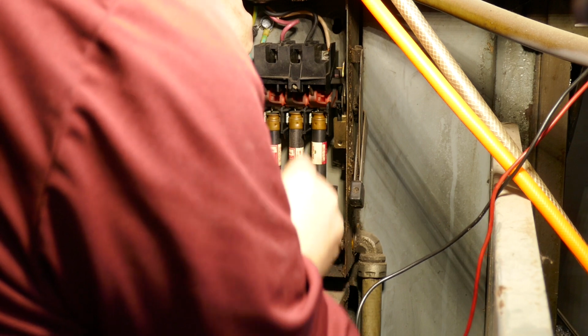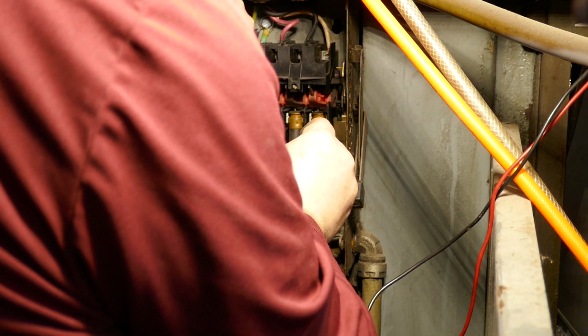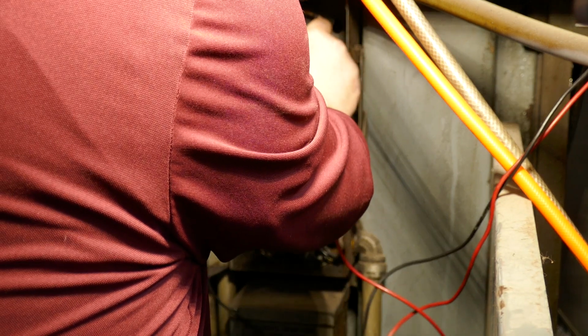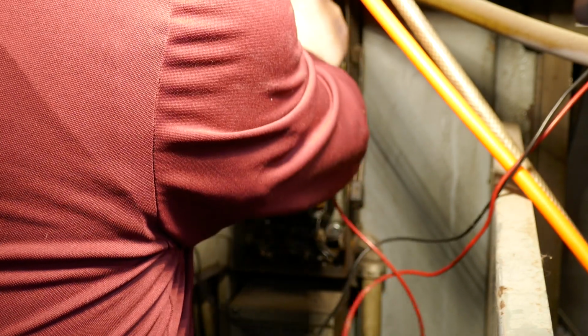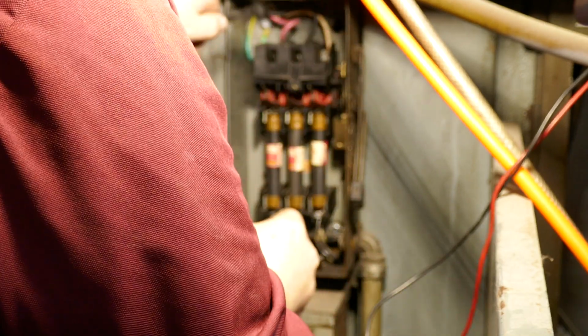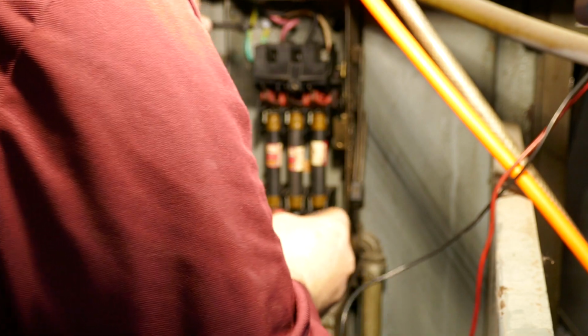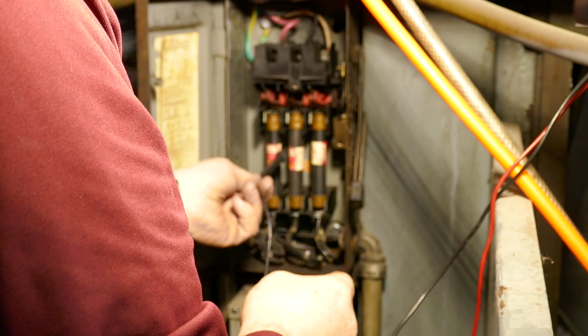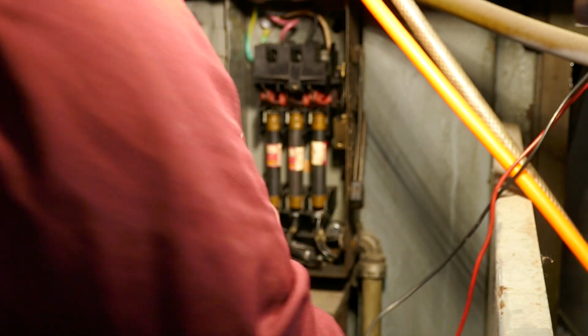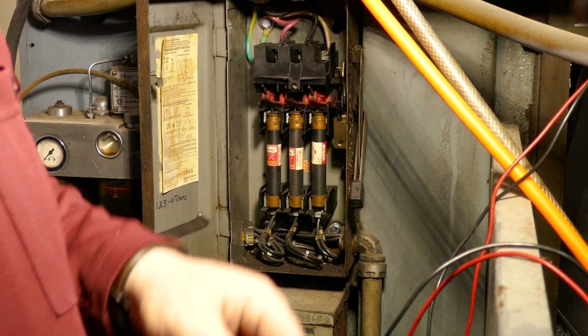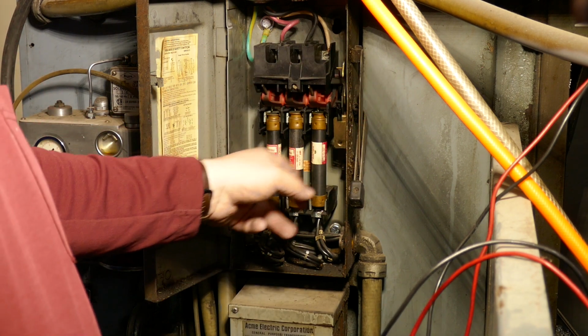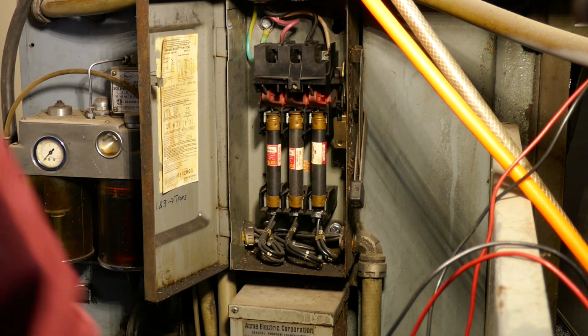Now it just occurred to me that because I have an isolation transformer, these may all be... okay, that one's 198 to ground, and that one's 116 to ground. So that one being 198 means the white one is the high leg, and I want to switch the black and white wires in order to have utility power on the two outer legs.